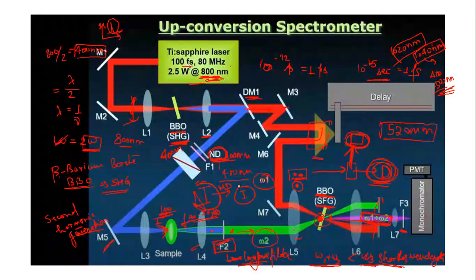This entire femtosecond setup depends on our laser source. Suppose it gets shut down, there will be nothing for the detector to detect, and you will not get the measurement. So for a good measurement and for the accuracy of the instrument, your laser should be quite stable during the entire process.